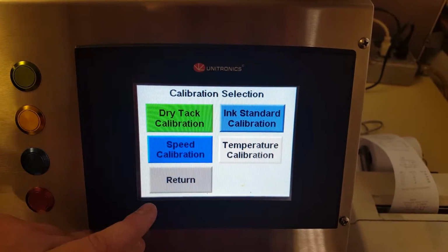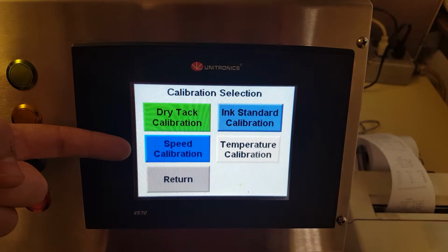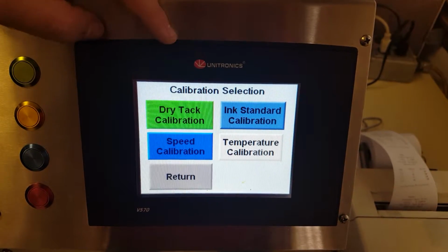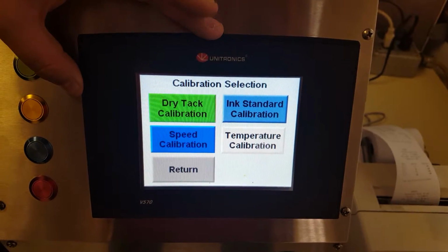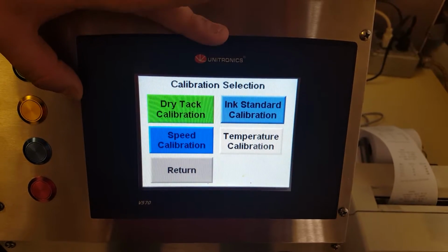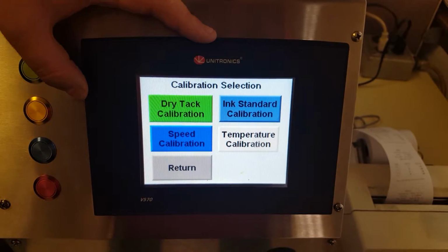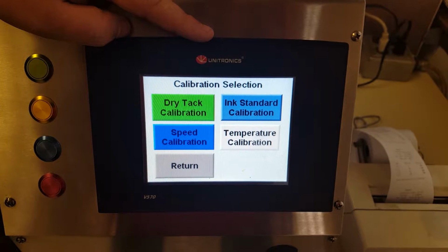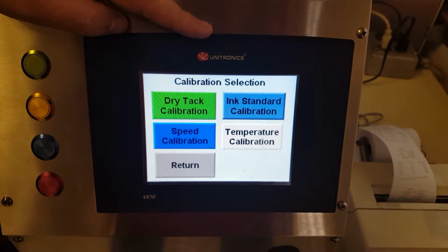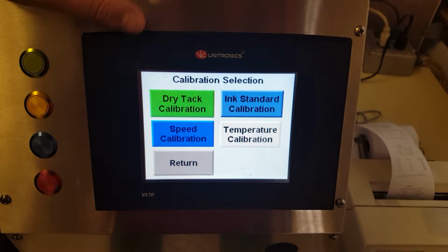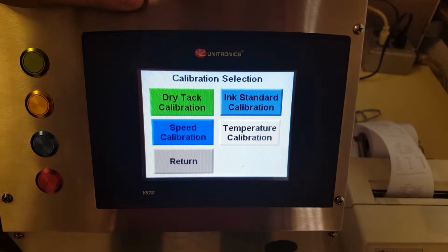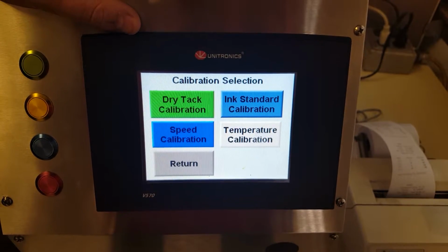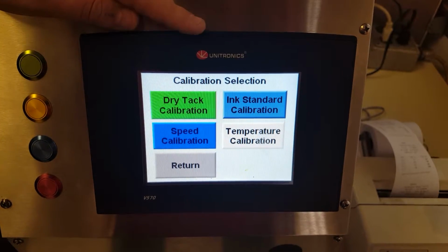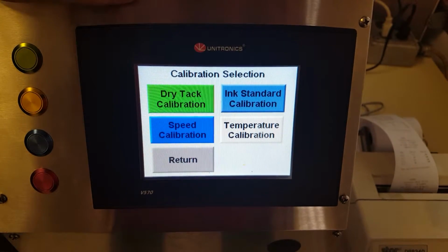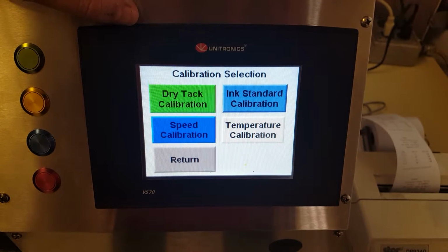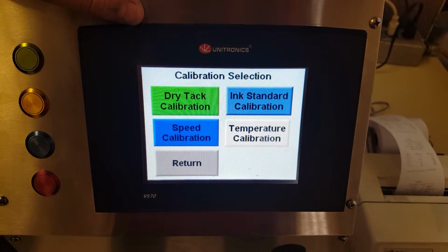Now we'll come back to this screen here, and we'll come to the speed calibration. I'm not going to click on the speed calibration and get into it because it's really straightforward, and for demo purposes I can simply explain that the way this works is the speed calibration is selected, and the rolls begin to turn, and a sensor inside this machine communicates with the PLC, establishing an RPM based off of how quickly the motor is running and things like that. Very simple, and it's really a one and done procedure. You run through the speed calibration one time and you very rarely have to set it up again.